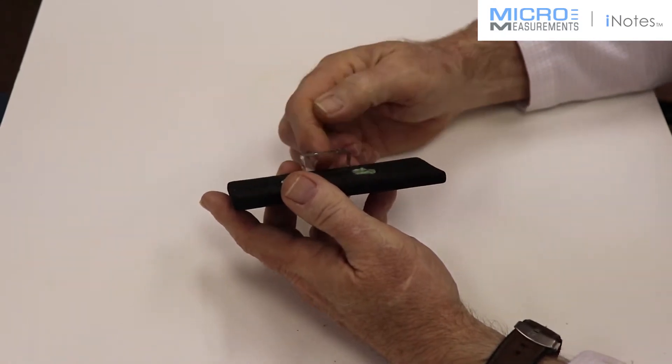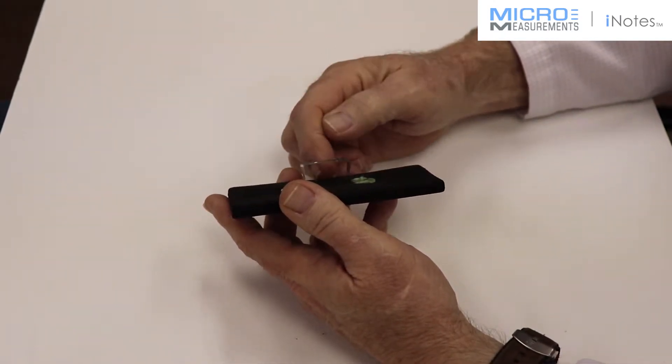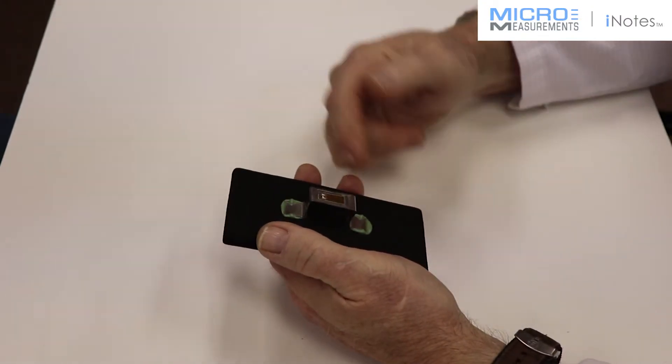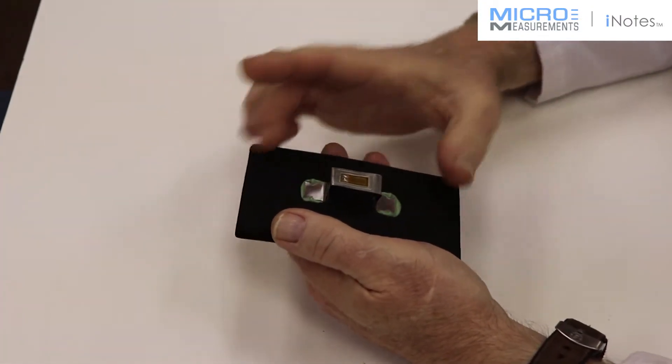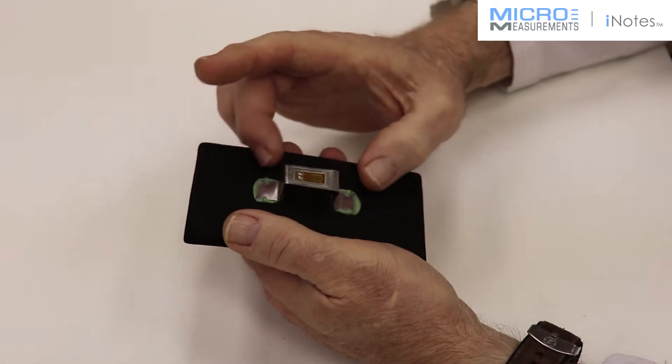the top will go into compression, the bottom will go into tension, and if you make it into a full bridge, you can calibrate it based on displacement or microstrain.